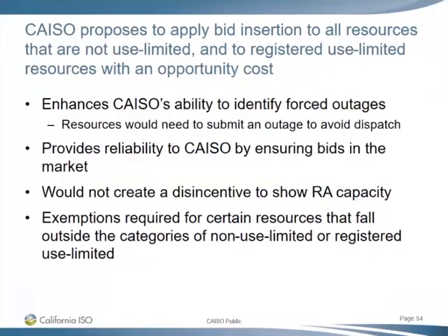You were breaking up a little bit there, Vic, but did you want us to take some feedback that you guys are a bit concerned with this part of the proposal? I think I just missed the punchline there, Vic. Basically, it's one of the integration questions of how all this hangs together. When certain units lose their opportunity cost grandfathering in a couple of years, what's going to happen if they get bid insertion at extremely low levels? They're going to be selected all the time and run out of starts, so then they'll be unavailable, and I don't know if it'll bring down their UCAP in a death spiral, or if there's no RAAIM or they have RAAIM penalties or whatever, but those types of issues do impact us directly.